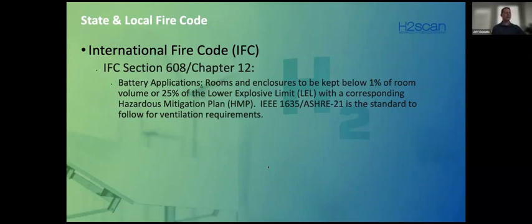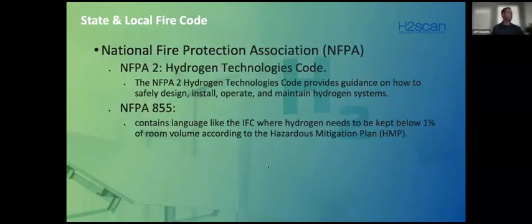AHJs are fairly flexible when it comes to accepting a mitigation plan, as long as it includes keeping that volume below 1% hydrogen in a given room. And again, the IEEE 1635 document is a key tool for calculating this. For the NFPA, we have NFPA 2, on how to design, install, and operate hydrogen systems. But for batteries, it's going to be NFPA 855, and that contains language, like I said, similar to IFC. NFPA used to be geared more towards just stationary battery systems, but 855 also includes BESS, or battery energy storage systems. It's an expanded document that was created to include all kinds of different battery technologies, not just for substations, but also for energy storage systems that could be for grid support, on demand, peak shaving, or even microgrids.